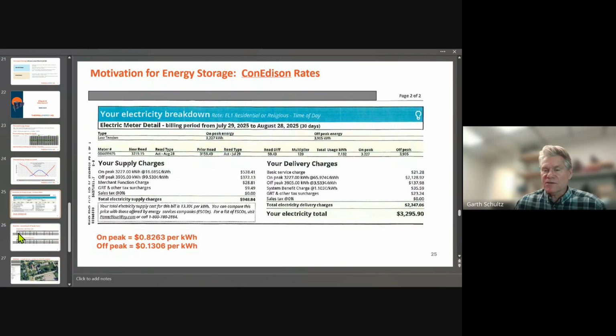What makes this opportunity so attractive is when you look at their on-peak versus off-peak energy costs: they're being hit with almost 83 cents a kilowatt hour, 16 hours a day, 5 days a week. For 8 hours at night and all the time on weekends, energy is available at 13 cents a kilowatt hour. That tells you that if you're electrifying this, you want to capture that energy when the timing tells you to.